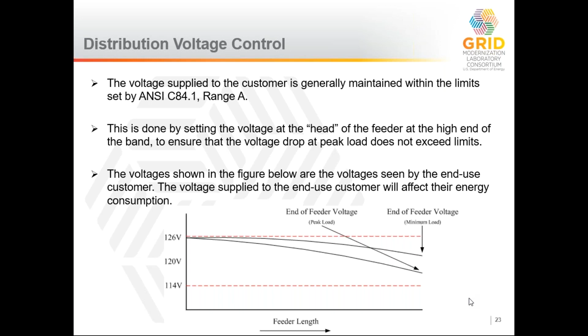For situations where the voltage drop can become too high, utilities will deploy what are called voltage regulators. These are smaller transformers that are designed to be able to regulate their output voltage within a range. These are electromechanical devices, and they can be referred to as tapping up or tapping down. What we see here is an example of two different tap settings, where the dotted line is a lower voltage tap setting, set at just above 120 volts, and the second one is set at 126 volts.